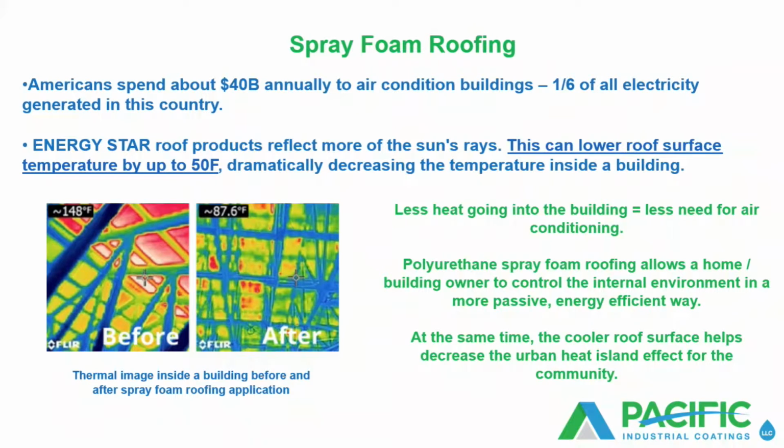We were taking readings on both sides, so you can see the big gains that we see in temperature drop, like you just illustrated earlier. In this case, it's well over 50 degrees F drop. 50 degrees drop, yeah. So it's simple to apply, and it's really a great application to reduce your overall energy costs by dropping the heat from the roof first. That's where the sun's going to hit right off the start.